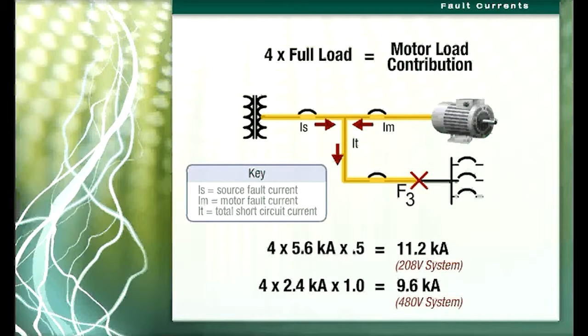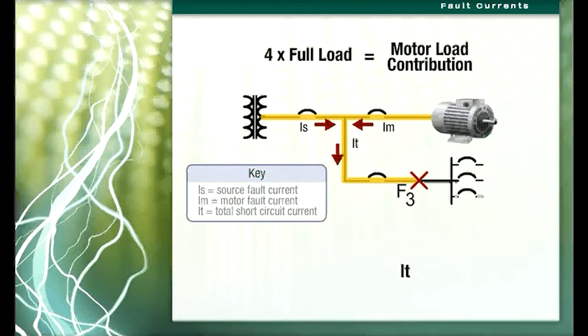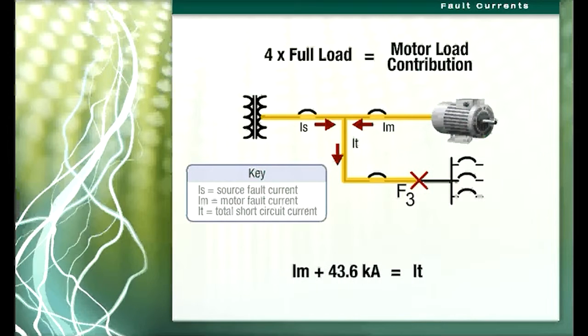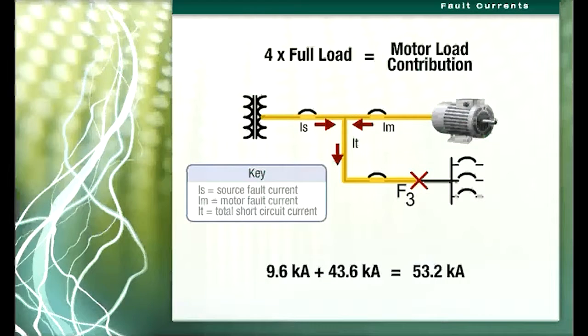Where the actual motor load is known, it can be used in this calculation. Therefore, the total short circuit current at F3 is the sum of the source fault current calculated earlier to be 43.6 kA, plus the motor fault current contribution of 9.6 kA, which yields a total short circuit current of 53.2 kA in a 480 volt system.